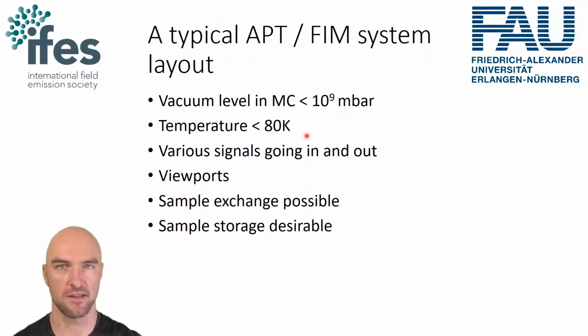So we need to have systems that cool with coolants other than liquid nitrogen. Historically, people used to use liquid hydrogen, which is a very, very good coolant with a temperature of about 20 Kelvin. But for safety reasons, this is not a preferred coolant these days. These days we use either closed cycle cryostats or liquid helium, and we'll go through that. In both cases, we'll go through how to generate the vacuum, how to maintain it, and how to measure it. And same for the temperature: we're looking into how to generate the low temperature and how to measure it.